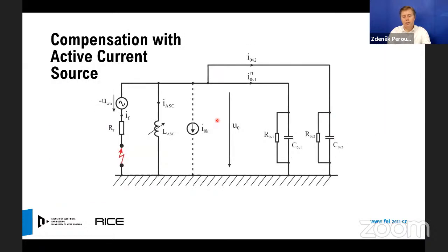So we have been thinking about how to overcome these constraints of the state-of-the-art technology, which has been operated in power grids for more than 100 years. And we came up with a power electronics-based solution. We came up with an active current source, which can operate together with the arc suppression coil or fully independently of it, and can replace the arc suppression coil in the grid. The problem is how to calculate the compensation current, which behaves based on Kirchhoff's first law. It means that if we are able to produce a compensation current with the same magnitude as the fault current, but opposite phase, then we will be able to mitigate the fault current and fully compensate the ground fault in the power grid.